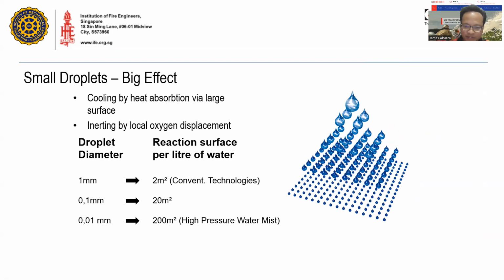to explain the meaning of small droplets having a big effect on fire suppression, imagine a conventional sprinkler or deluge system, where the actual diameter of the droplet is 1 millimeter. Now, if you lessen the diameter of the droplet to 0.1 mm, thereby pushing more pressure, there will be a wider range of area of protection, or heat absorption, or local oxygen inerting, of 20 square meters.